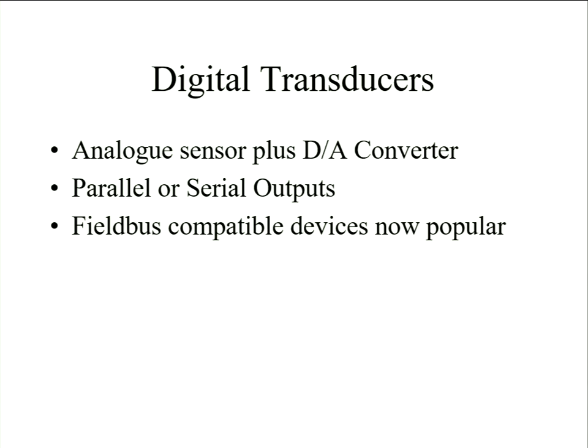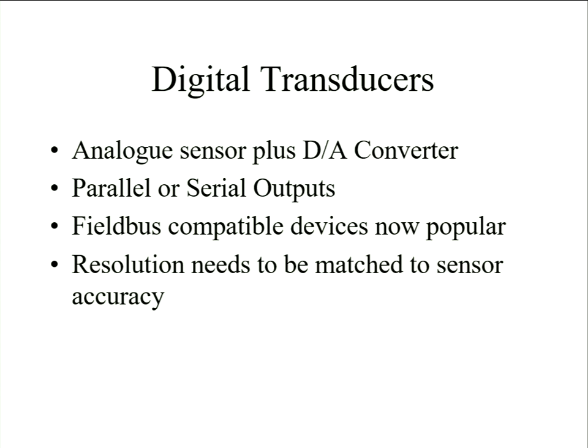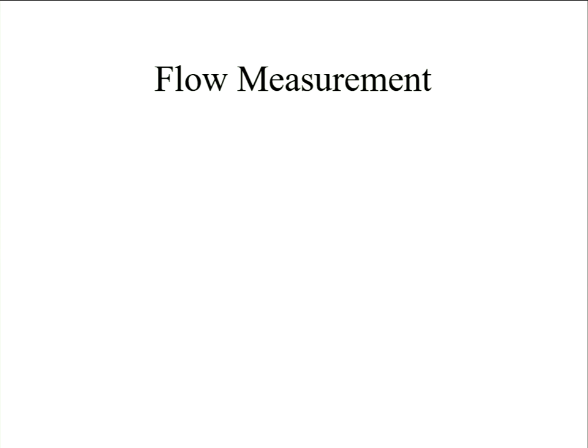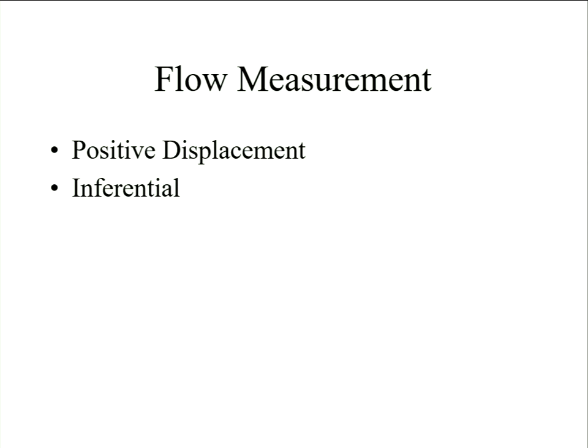Turbine meters, ultrasonic meters, and magnetic, so for conductive fluids only. Then there's our old friend, the orifice plate. There are still masses of those. They're relatively simple, apart from the fact you've got to have a carrier, you've got to have an inspection regime, and if you're using it for fiscal purposes, then you've got to be very precise in knowing the measurements of your orifice plate. Otherwise, you find that somebody is out of pocket somewhere.